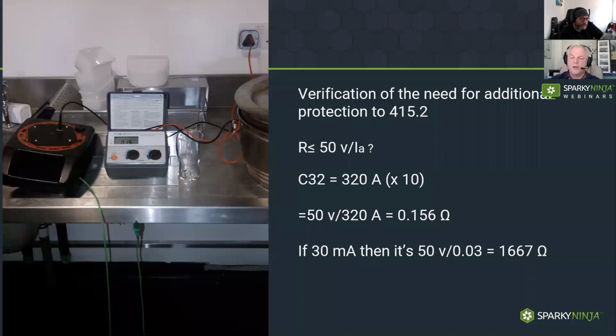If they're not an extraneous conductive part, you can find that by doing a resistance measurement. If you had done that measurement and had a value of over sort of 22,000 ohms, then it doesn't constitute an extraneous conductive part.